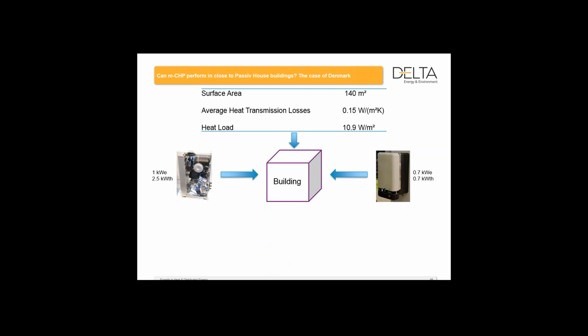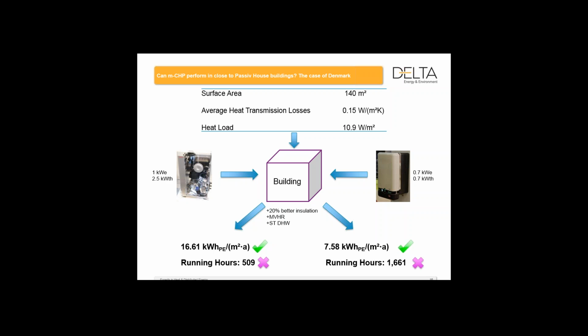But how does this picture change if we try to push the internal combustion engine below the required primary energy demand? Well, this would require some significant additional investment in better insulation of the building, mechanical ventilation with heat recovery, and solar thermal hot water production at the least. In such a building, both the internal combustion engine and the fuel cell would meet the primary energy target, but at the expense of their running hours being significantly reduced, which makes this solution uneconomical.